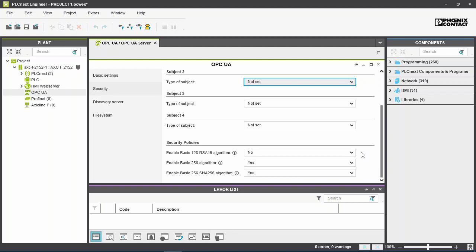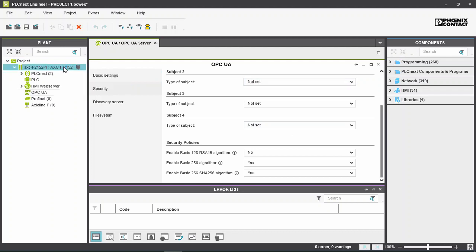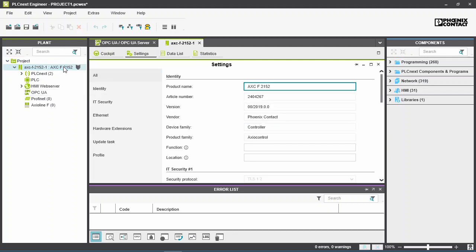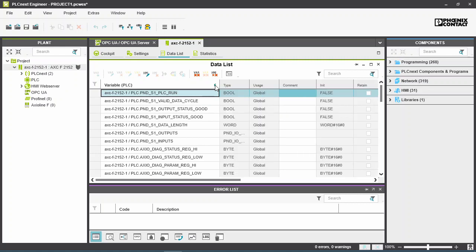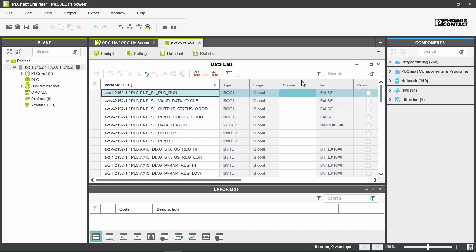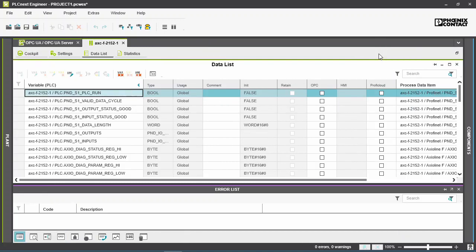Now open the PLC data list. Double-click on the controller. Unhide the columns related to the PLC variables. The variable window can be expanded if needed. Select which variables should be accessible through the OPC server.